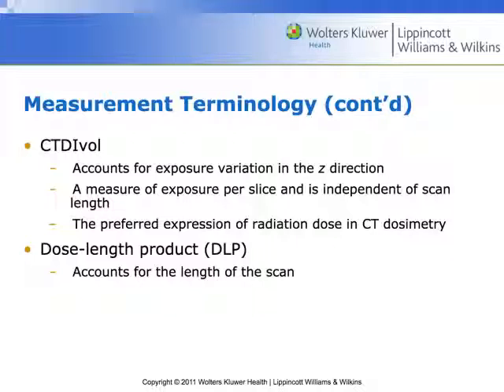Finally, from CTDI volumetric we can calculate a dose length product — the DLP. The machine calculates it for us; it accounts for the length of the scan. It's basically the CTDI volumetric multiplied by the scan length. So the CTDI is the smaller number and the DLP will be a bigger number.